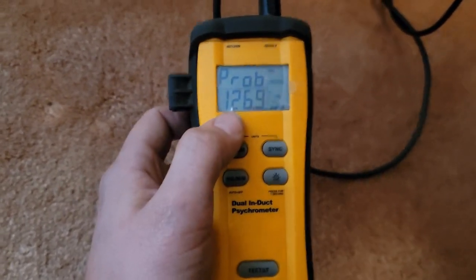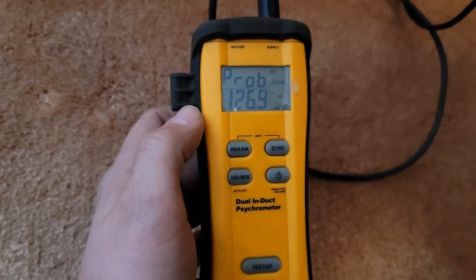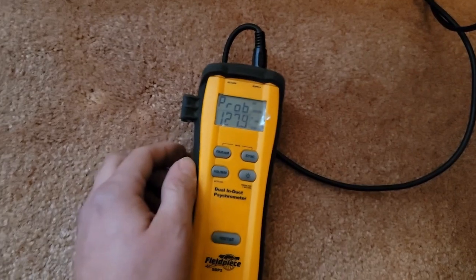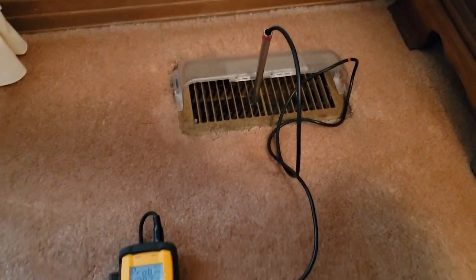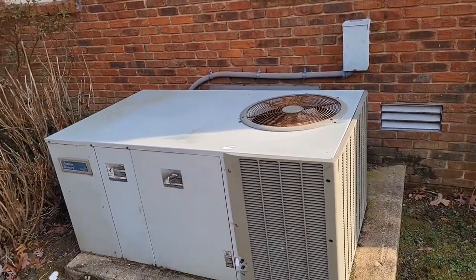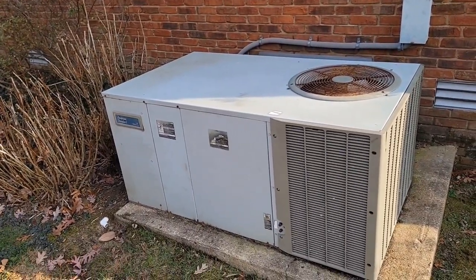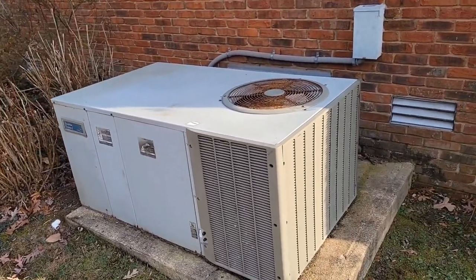Auxiliary heat should be on now. Using the dual in-duct psychrometer to measure supply temperature - it's 125, now 126, now 127 degrees and going up. It was 97 before, so now it's much hotter. Two new breakers and one lug later, the unit is working properly, auxiliary heat is coming on. They should be nice and warm - that was about a $300 call.